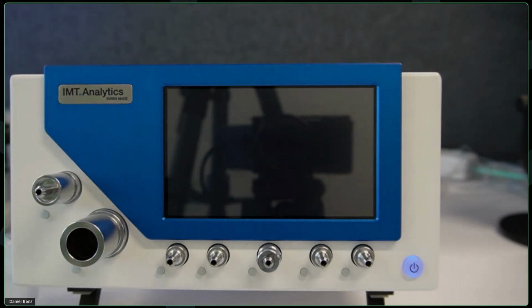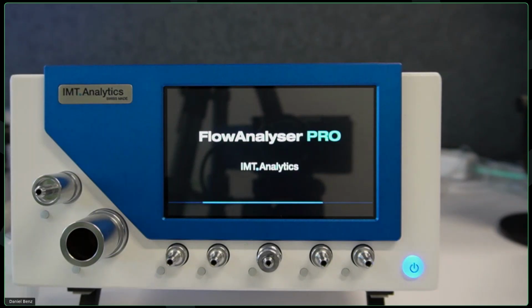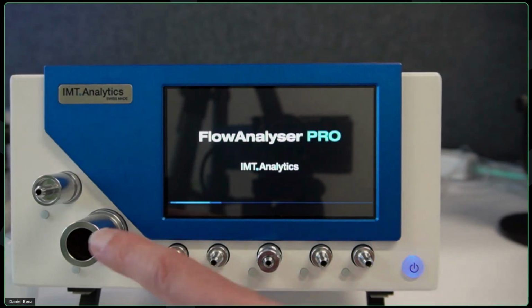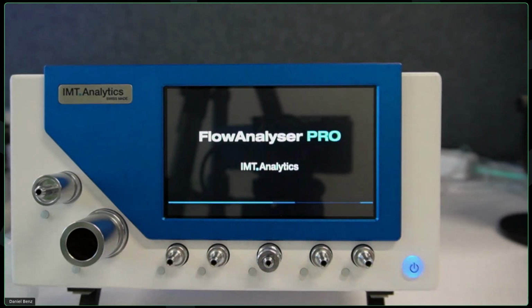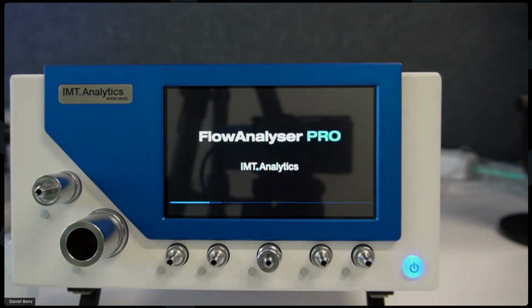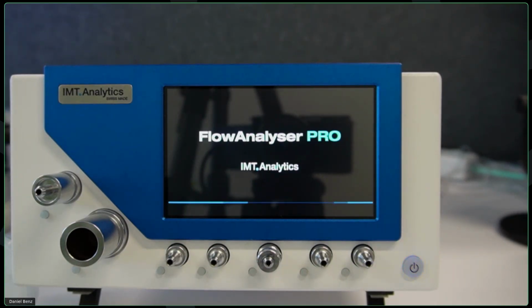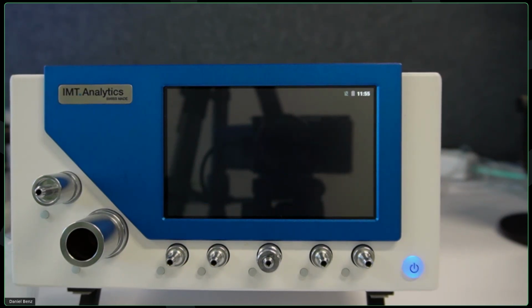The main port you would be using if you test ventilators is our main flow channel. That's the one here. This is going to be used for the vast majority of the applications. It is a bidirectional flow channel. It runs through the whole device and can measure flow rates in the range of plus and minus 300 liters per minute with an industry-leading accuracy of 1.65% or 40 milliliters per minute.